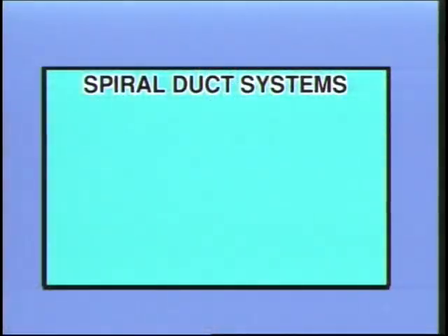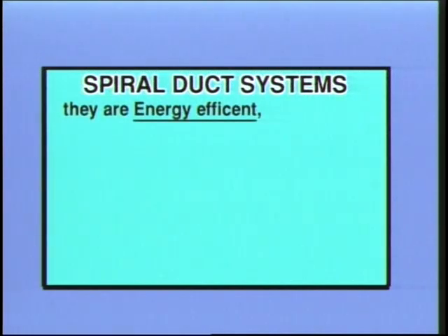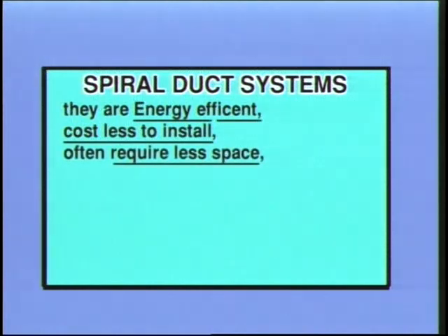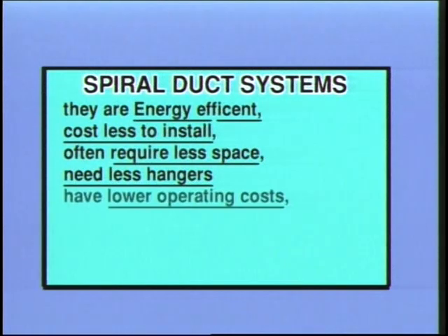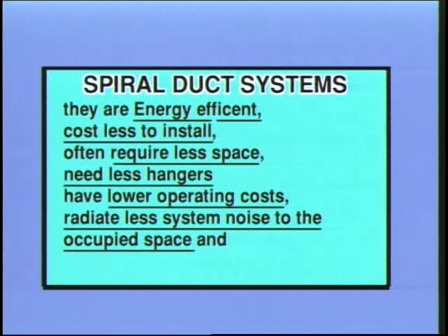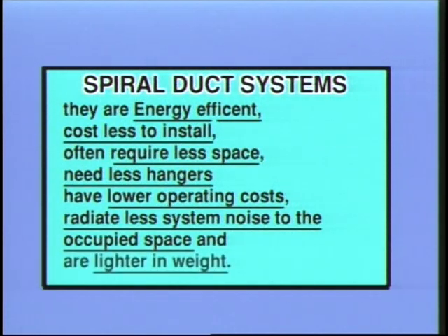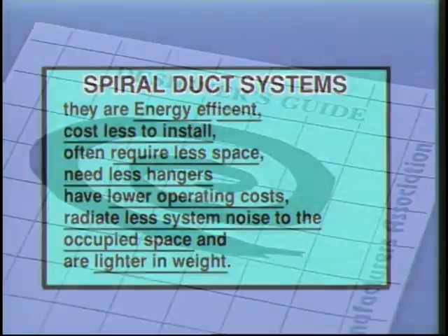In summation, the following are some of the reasons why spiral duct systems should be used. They are energy efficient, cost less to install, often require less space, need fewer hangers, have lower operating costs, radiate less system noise to the occupied space, and are lighter in weight.